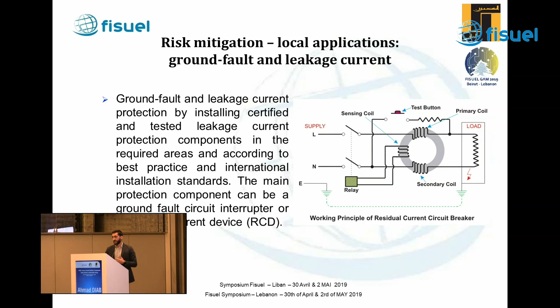we have faced some issues with these devices continuously undergoing nuisance tripping. We can say that this is mainly due to some noise in the utility network itself, and also the recurrent power outages, which require switching from the utility network side to the diesel generator side every 4 to 6 hours or so outside of Beirut.